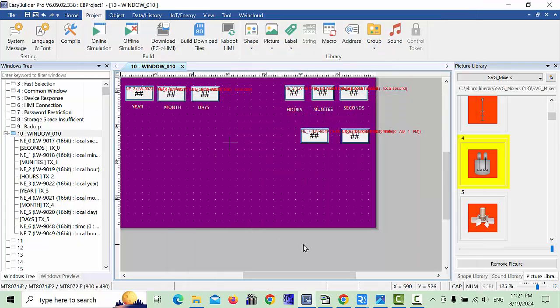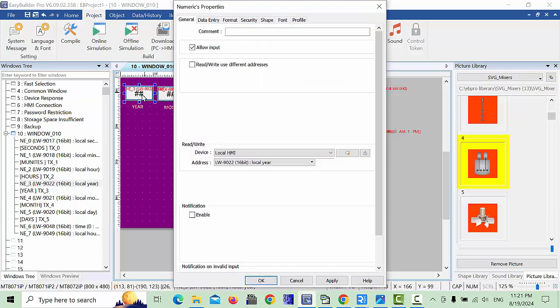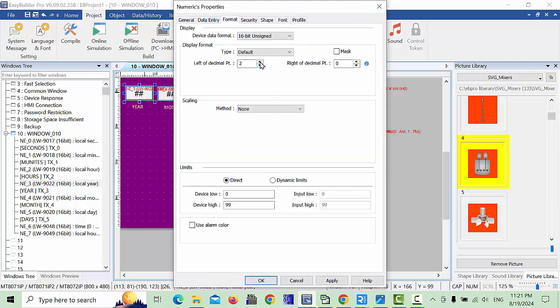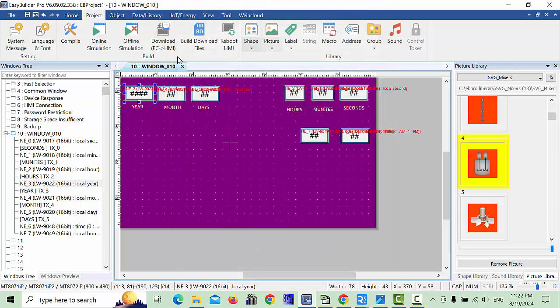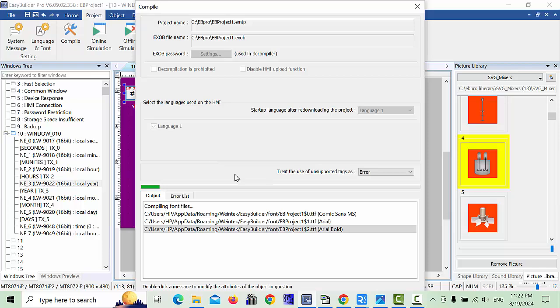In the year field, go to Format settings. The 'Left of Decimal Point' value needs to be set to 4 instead of 2, because the year is a 4-digit number. For all other time and date fields, 2 digits is correct, but for the year you must put 4. Click OK and download to the HMI again.